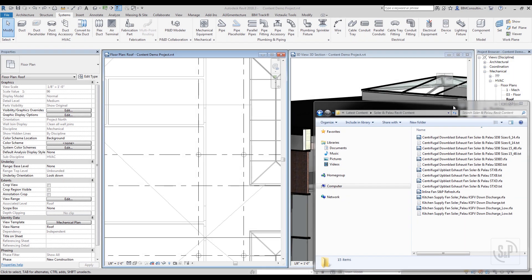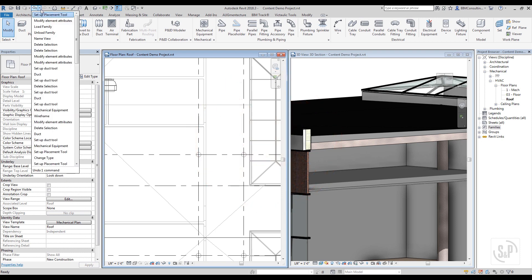Soler & Palau's Revit content comes in two types: those with type catalogs and those without. Those leveraging type catalogs are recognizable by the accompanying txt file of the same name. Never drag and drop the content from Windows Explorer into the Revit design window. This bypasses the type catalog and the content size and information will be invalid.